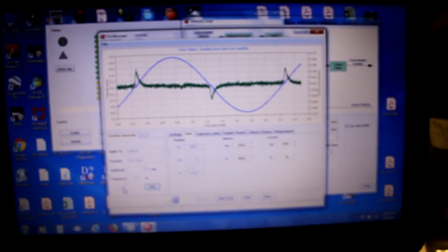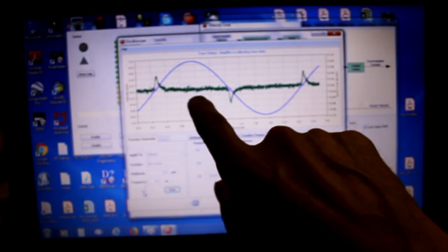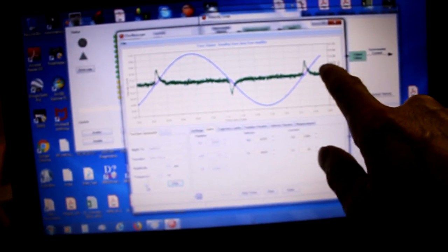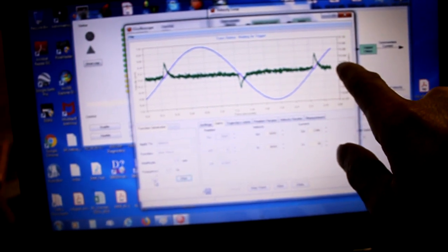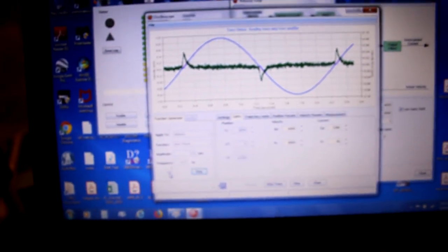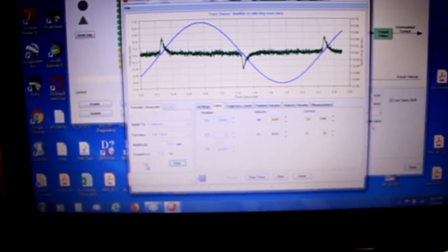There you can see the gain. I've got a pretty high integral gain and a pretty high velocity loop proportional gain, and you can see I just have a fairly small error. This is the error, and right where we cross zero, there's a little error. It's about 5% for about 100 milliseconds or so. So it's not too bad.